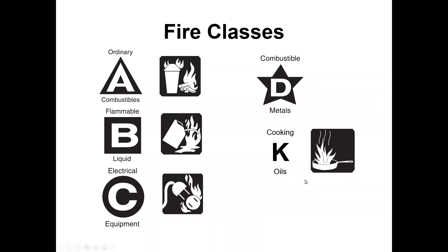There are basically three main classes of fire. Class A involves combustibles: paper, wood, clothing, carpeting, furniture. Class B is a combustible or flammable liquid — combustible liquids have a high flash point like motor oil, while flammable liquids like gasoline have a very low flash point. Class C is electrical, and we classify it differently because whatever you use to extinguish it must be non-conductive, otherwise you'll get shocked.